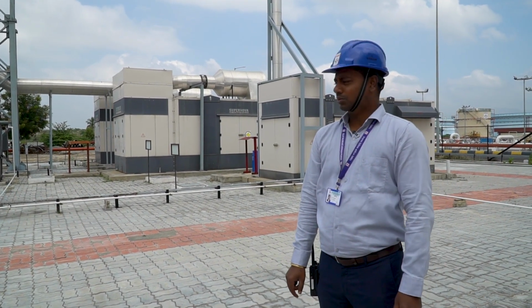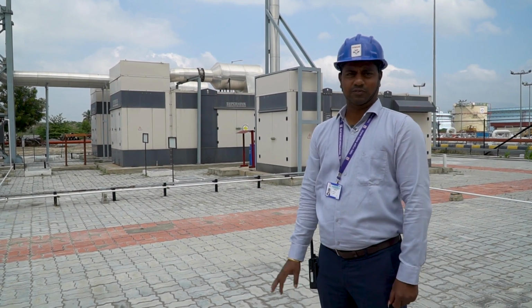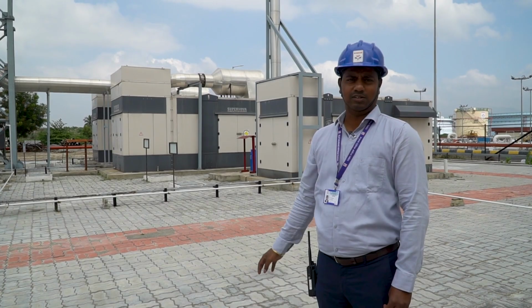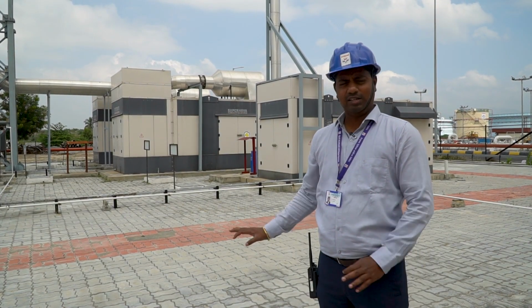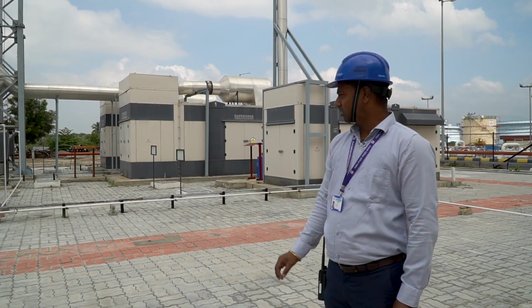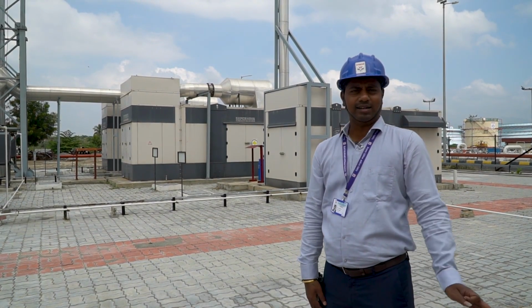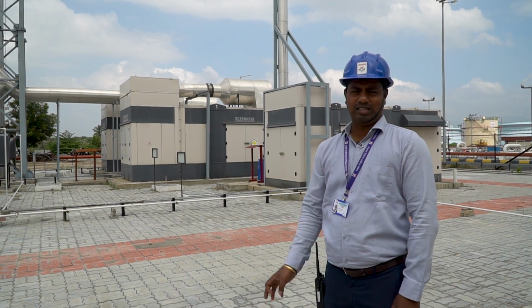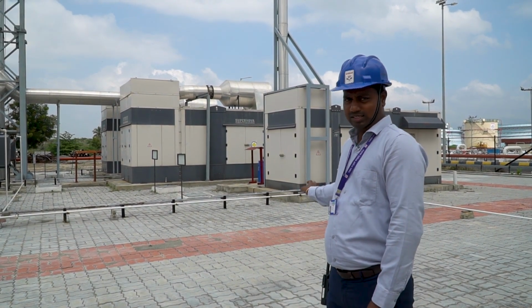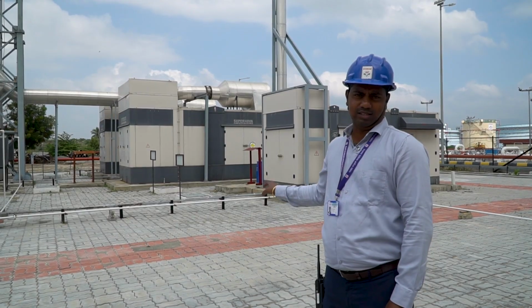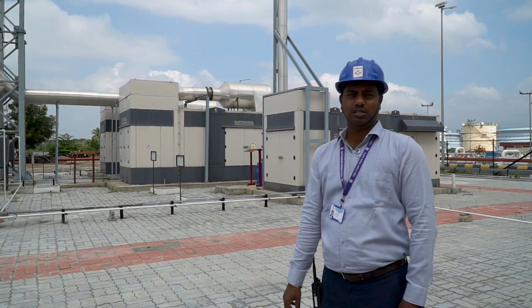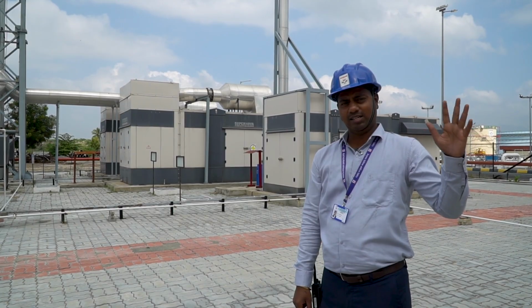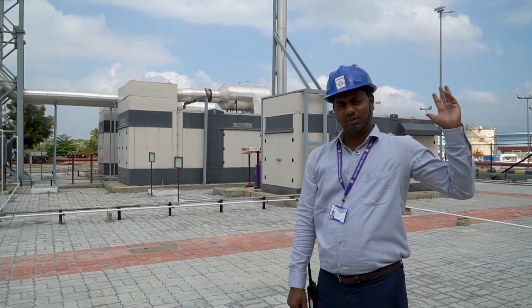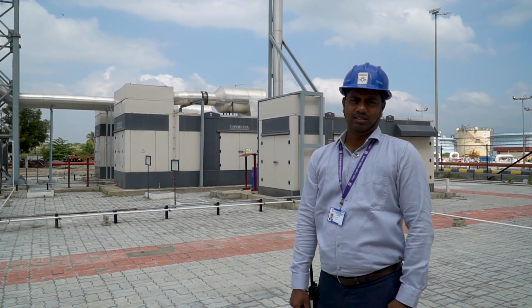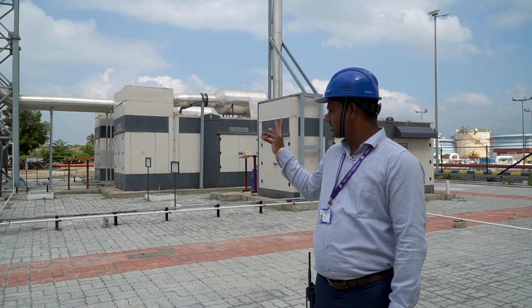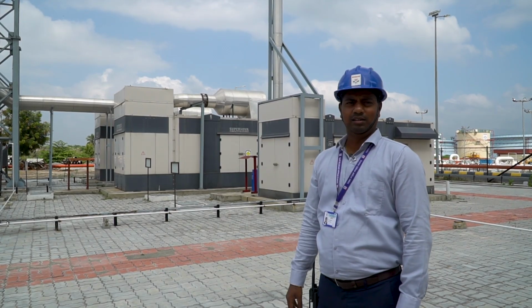plant. Periodic maintenance is a must for any DG set, like air filters and oil filters have to be changed at every scheduled maintenance activity. This 400 kVA DG set will switch on when the plant is not under operations, at night time when there is no power supply, and this emergency DG set will provide power to the emergency panel. From the emergency panel it will go to the UPS, and from there it will go to the critical instrumentation. So these 2 DG sets are enough to run the entire terminal power requirement.